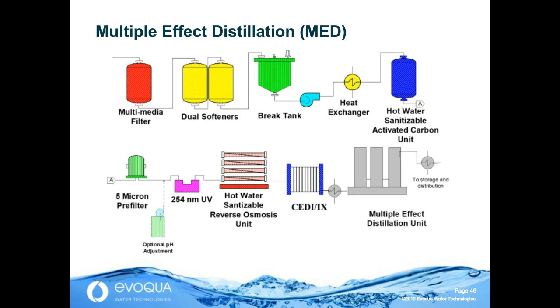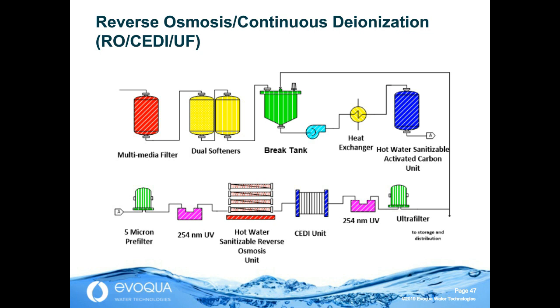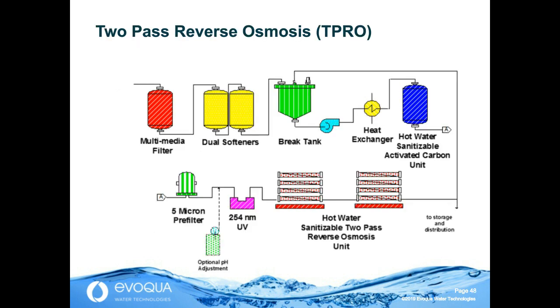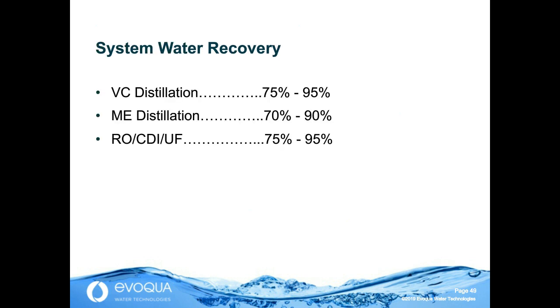We looked at a typical single-pass RO CDI UF system, so we're going to move on. And two-pass RO, we have also stated, can make WFI. Now, in water recovery, VC distillation I've seen as high as 95%. Depending on the pre-treat and the feed water, the recovery may be as low as 75%. In the same range, but because there's typically water loss from a membrane system plus still blowdown, this configuration can be the lowest.